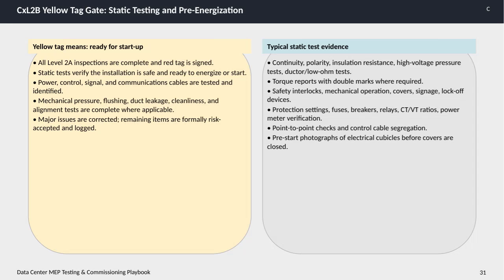This slide focuses on the CxL2B Yellow Tag gate, which represents a static testing and pre-energization phase in data center MEP commissioning. A yellow tag means the system is ready for startup, indicating all Level 2A inspections have been completed and the red tag has been signed off. At this stage, static tests are conducted to confirm that the installation is safe and ready to be energized or started. This includes thorough testing and identification of power, control, signal, and communications cables. Mechanical checks, such as pressure, flushing, duct leakage, cleanliness, and alignment tests, are also completed where applicable. Major issues identified up to this point must be corrected, and any remaining concerns are formally risk accepted and documented.